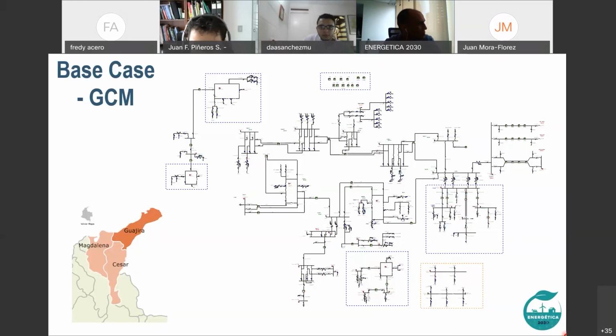And then we were building a general purpose model for protection analysis that integrates several kinds of control strategies: the reactive current, the dynamic reactive current support, a limitation of the current, all what David was describing. In that case, you can use it for protection. But when you have the project and you place the wind park, at the end the best is to have the model from the manufacturer that you can evaluate. But for analysis, planning, and estimation of what will happen, it is valid. And we were testing with EPRI. The EPRI model even had a validation with a real inverter. Maybe David can explain a little bit more.